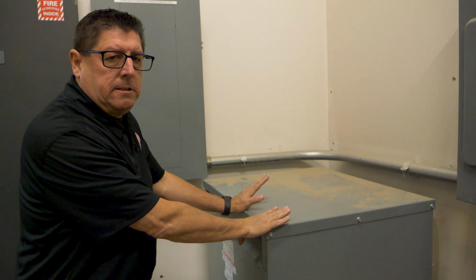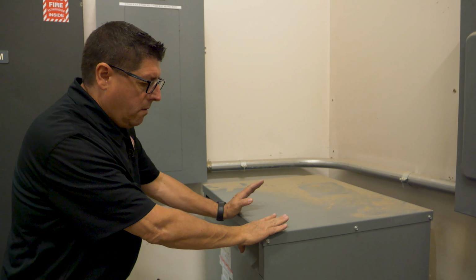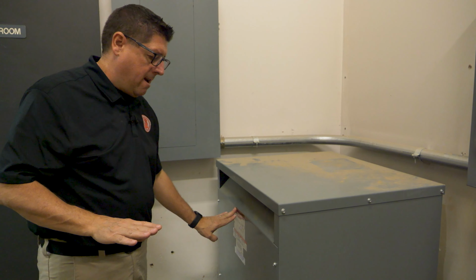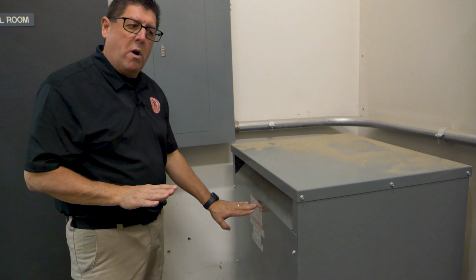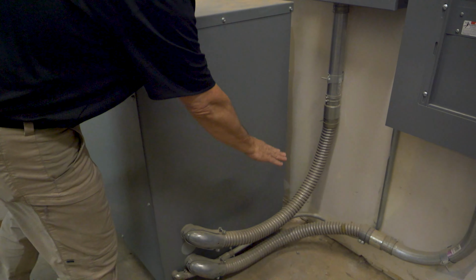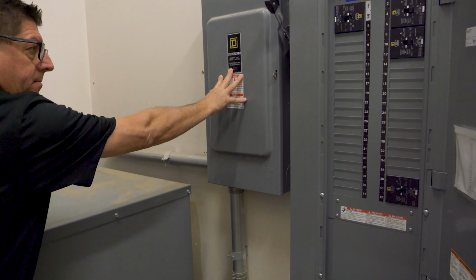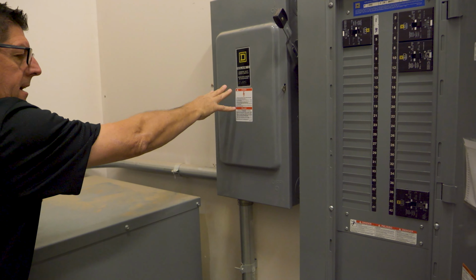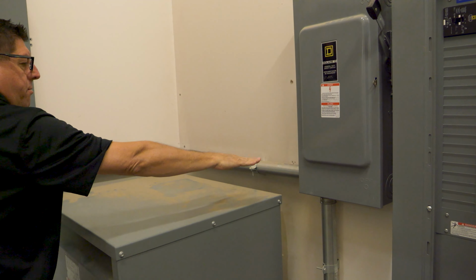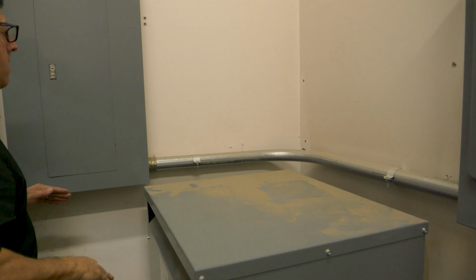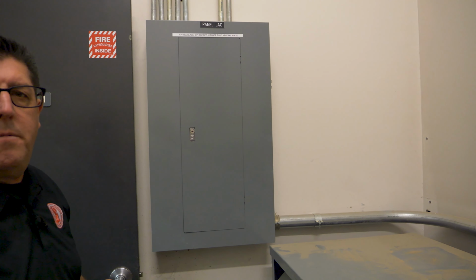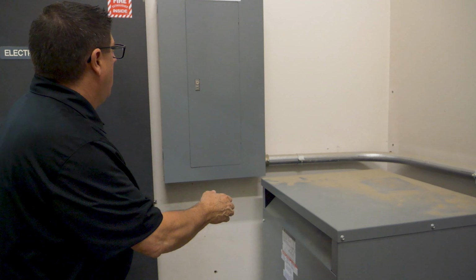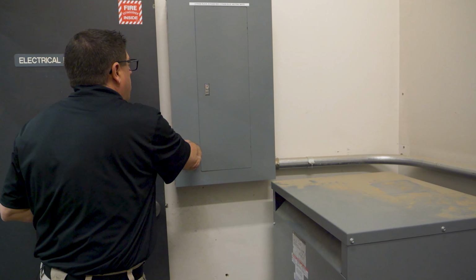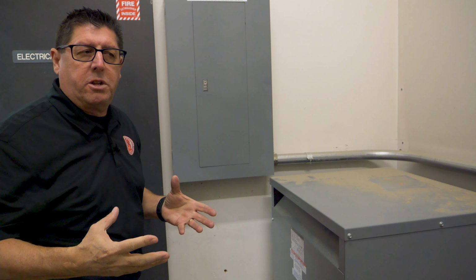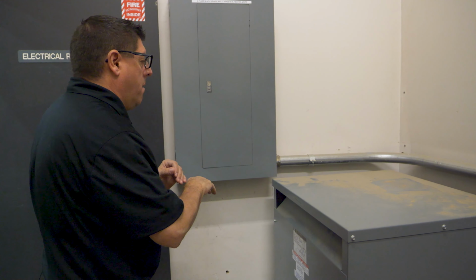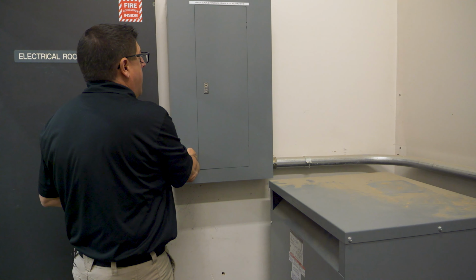The transformer, being a step-down transformer, releases, instead of the 480, it comes out at 208/120, through this conduit, through this disconnect. From this disconnect, it's providing electricity through conductors and this conduit to this electric panel. Before opening this panel, I verify it does not have current by using my right hand or a non-contact voltage detector. Again, hair on my knuckles would stand up or I'd feel static.